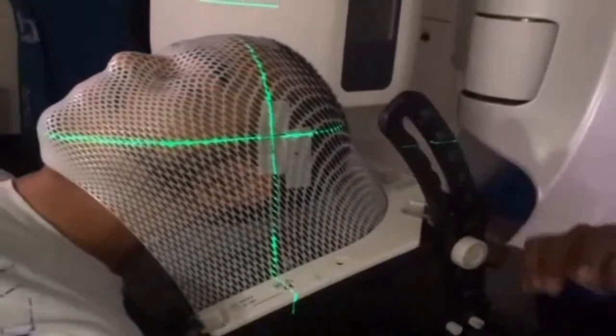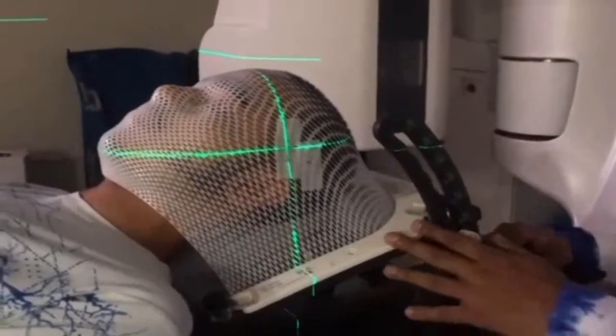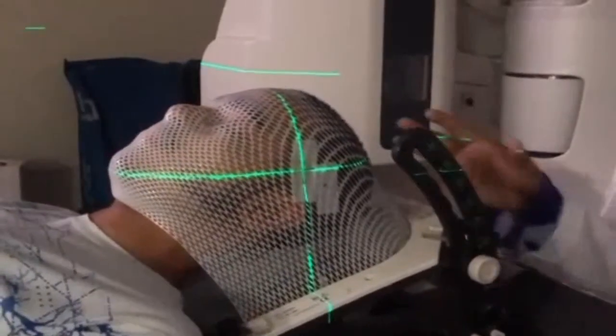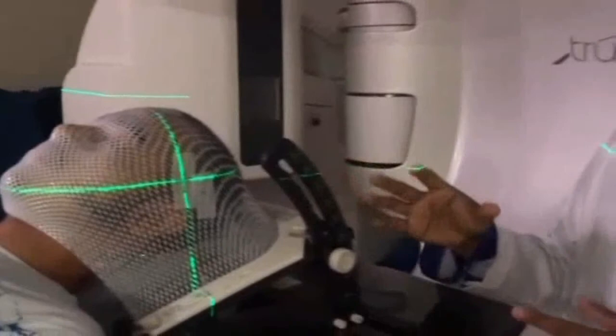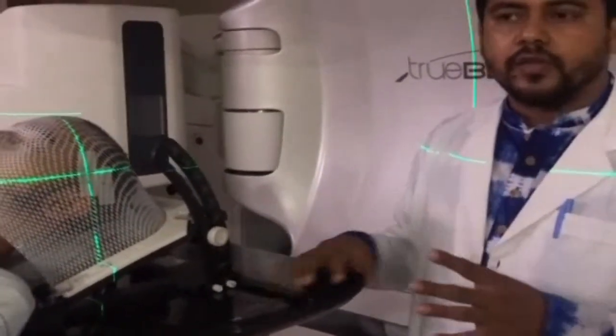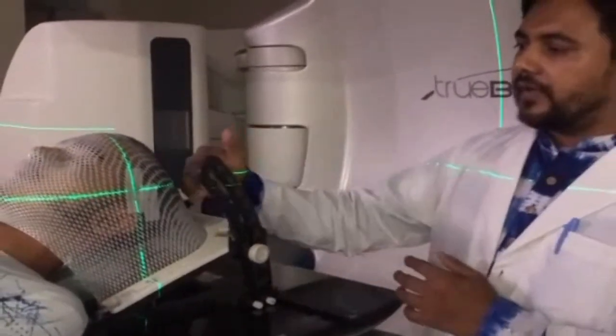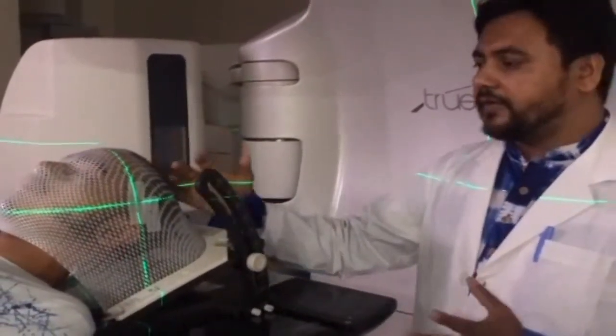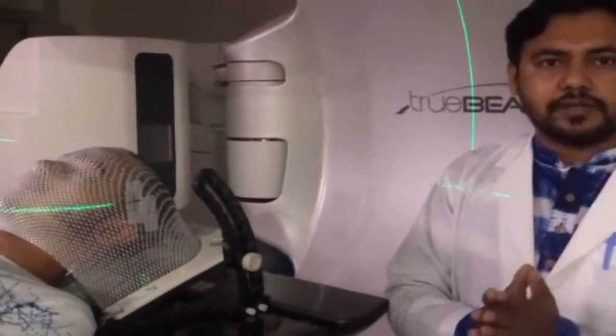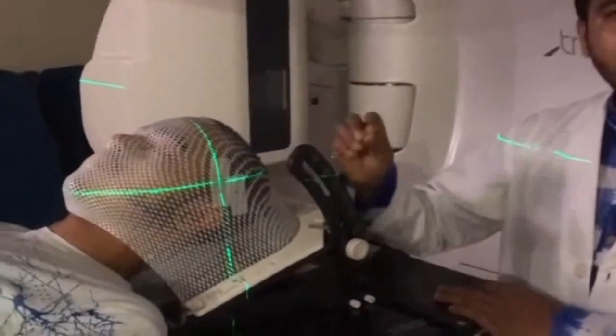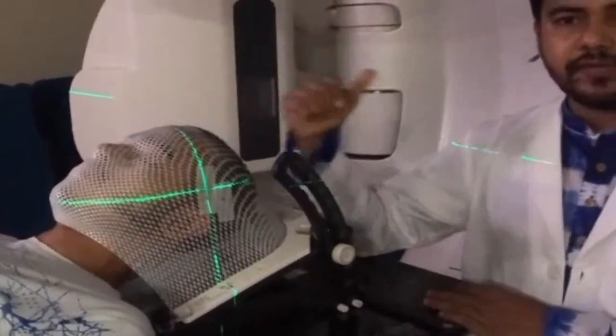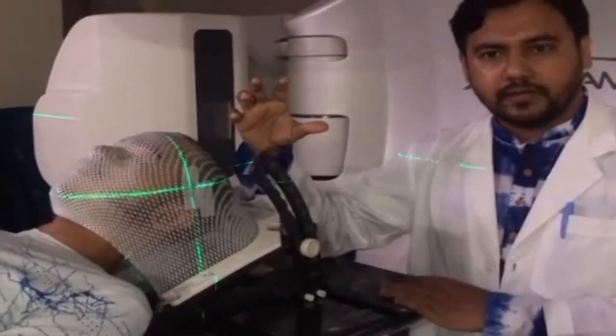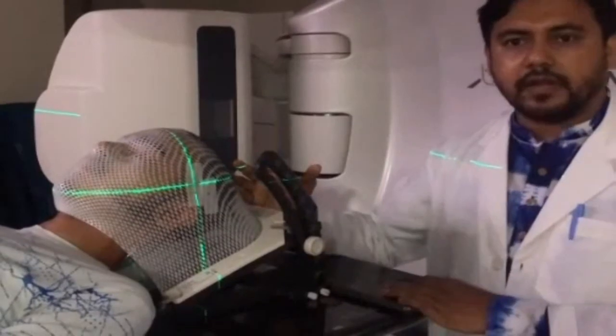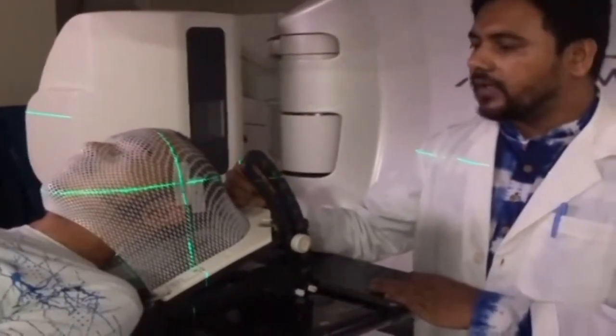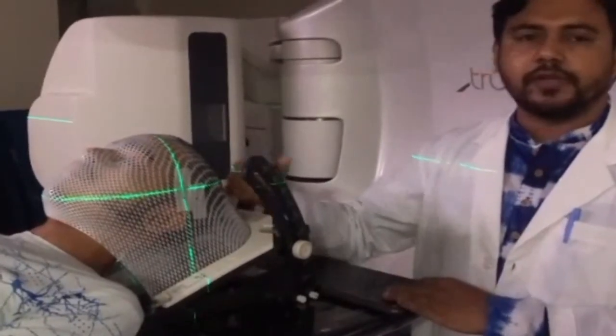Before treatment, we have a special facility, an online verification system. If during the treatment or before the treatment the patient is shaking or tilted or moving somewhere else, then this online verification system tracks this movement. The difference between the real distance and the displaced distance, this online verification system will correct it. It will correct to sub-millimeter accuracy. This is the special beauty of this accelerator, and it is a very high-tech machine. There are few such machines in our country, so fortunately we have this type of machine.